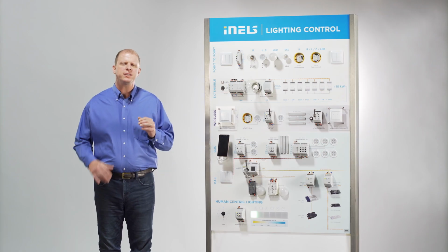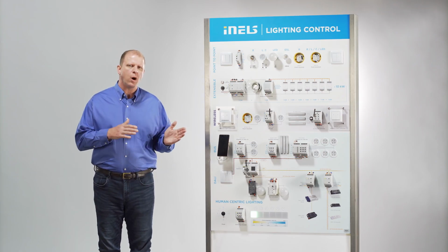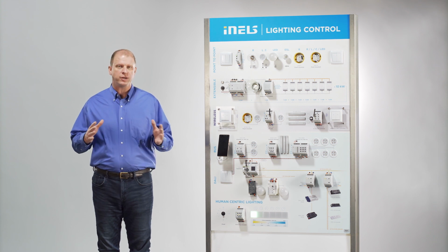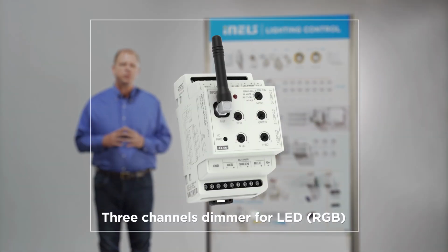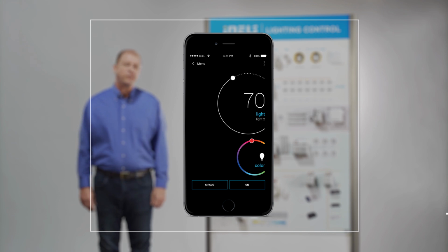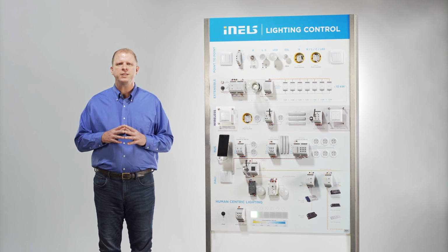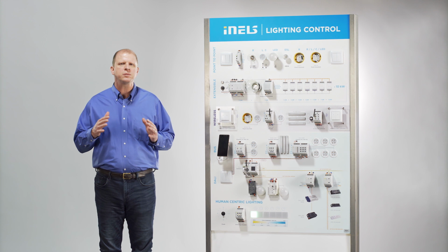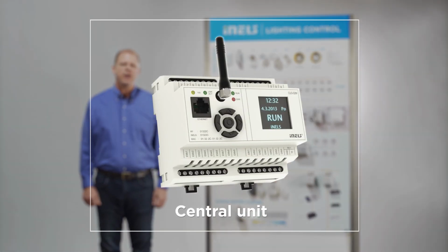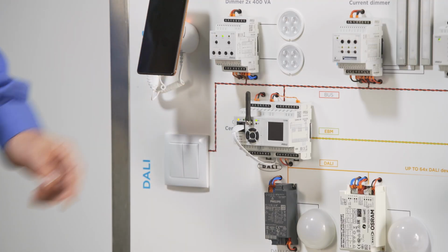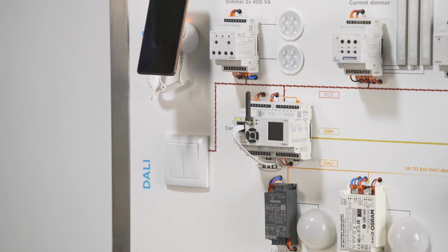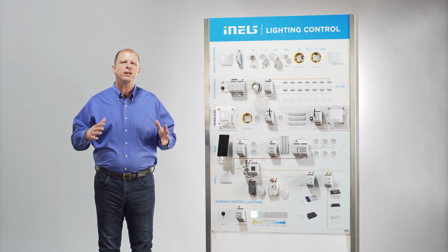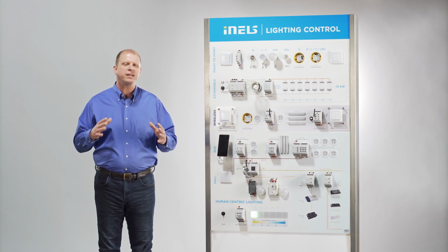And in this variant, there is the additional possibility of dimming one or more colored LED strips of various lengths. These are easiest to control via a mobile application or via the touchscreen of the RF touch unit. Here too, the iNELS RF system can be controlled by the iNELS bus elements if a central unit with the wireless module is present in the installation. An increase in signal range can be achieved by using an external antenna that can be screwed in to either the ELAN or CU3. Let's now look at the most advanced variant in the field of lighting control.